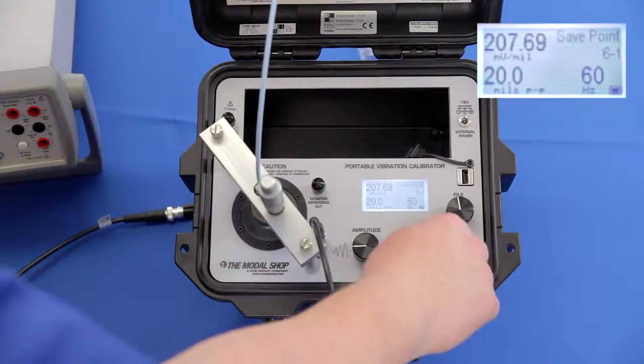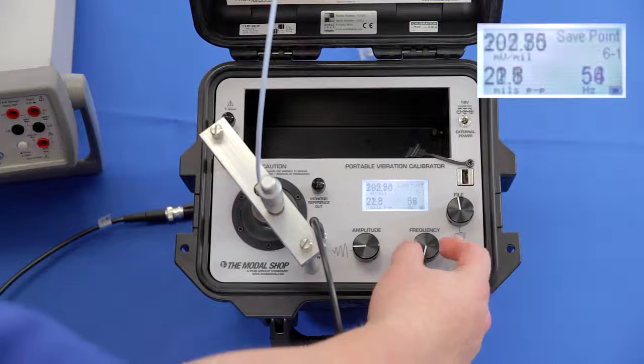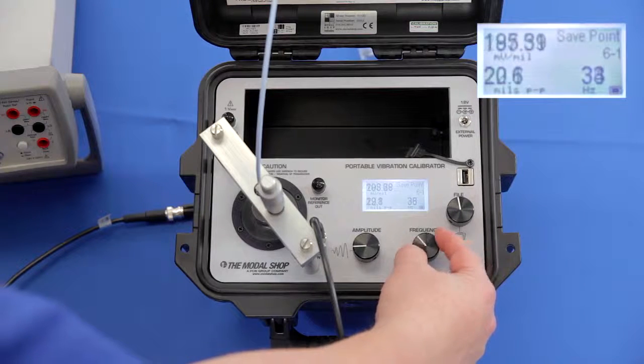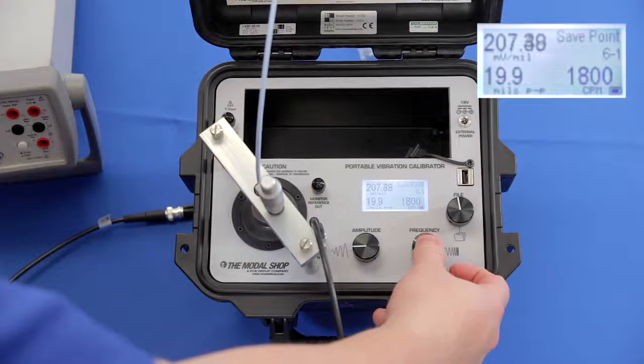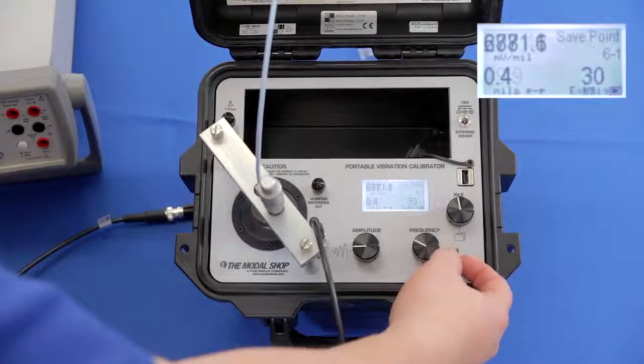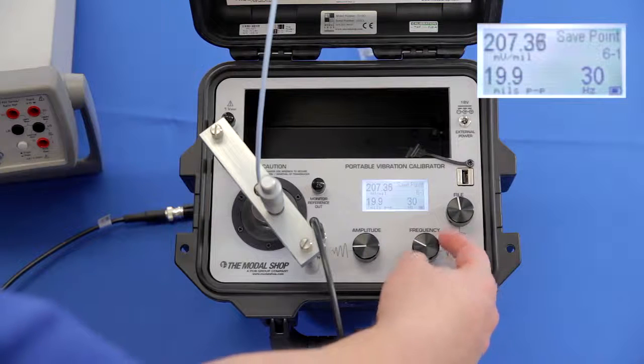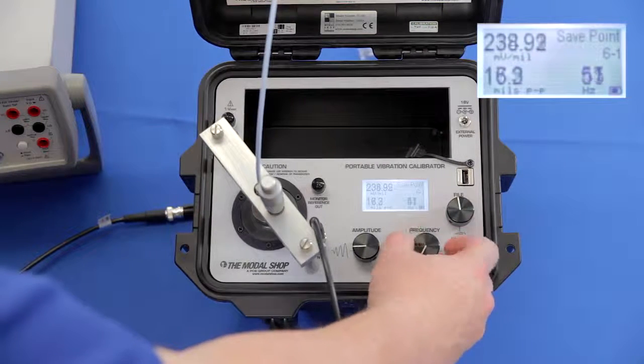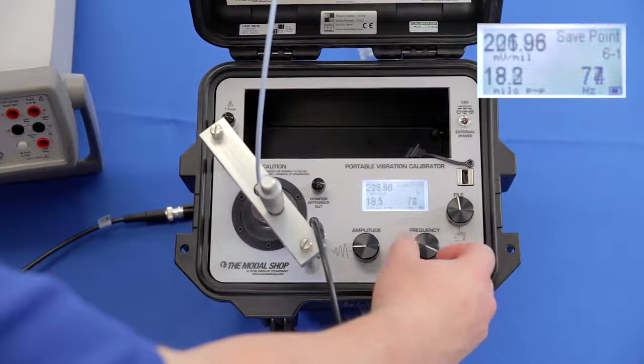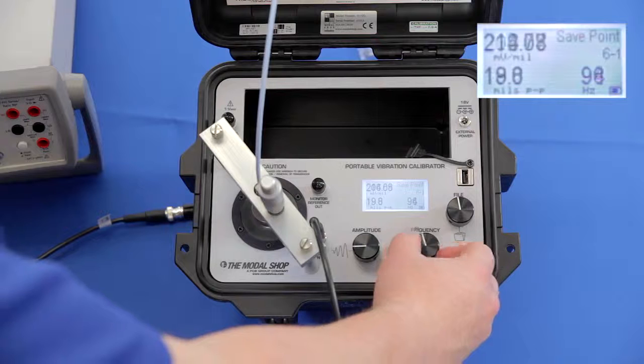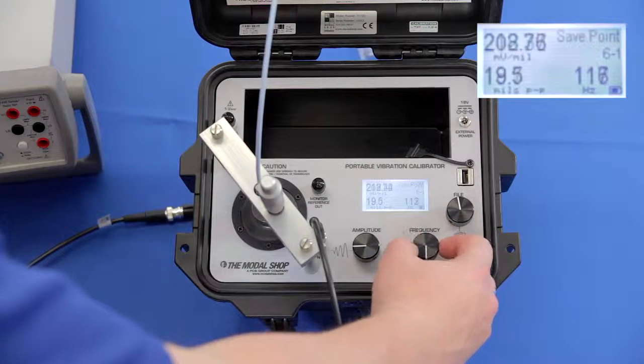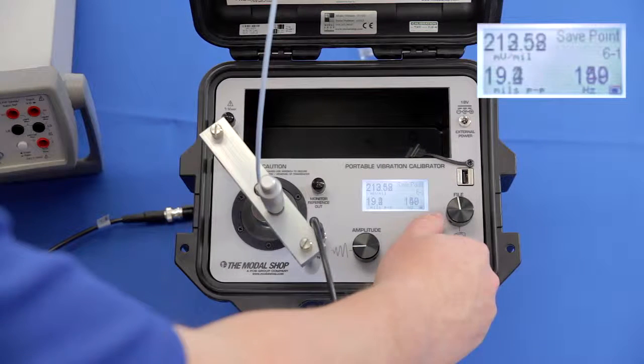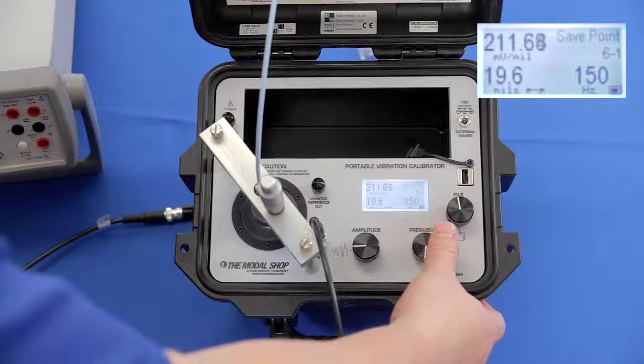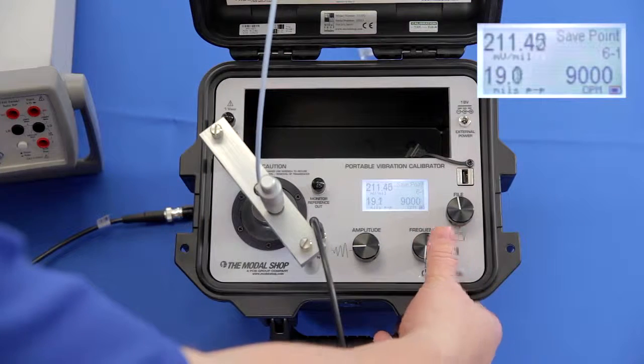Another thing I can do with the calibrator is do a frequency response check. You can see I can rotate the frequency down to 30 hertz, or 1800 cycles per minute. Check the output at that point, 207, and I can rotate up to 150 hertz, or any point in between. And you'll notice on our proximity probe that the output starts to increase just a little bit when you get up to these high speeds. 150 hertz, 212 millivolts per mil. This is 9,000 cycles per minute, so I'm a little bit high at that point.